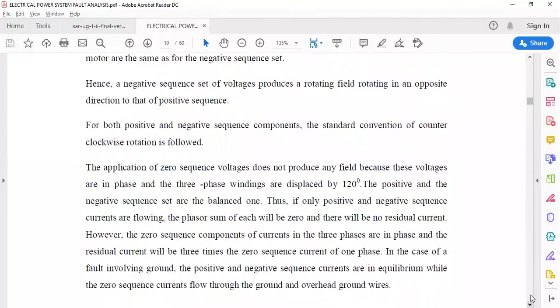The application of zero sequence voltages does not produce any field because these voltages are in phase while the three-phase windings are displaced by 120 degrees. So there is no such impact of zero sequence voltages, as they have zero phase displacement from each other in the three different phases. The positive and negative sequence sets are the balanced ones. Thus, if only positive and negative sequence currents are flowing, the phasor sum of each will be zero and there will be no residual current. However, the zero sequence components of currents in the three phases are in phase and the residual current will be 3 times the zero sequence current of one phase.